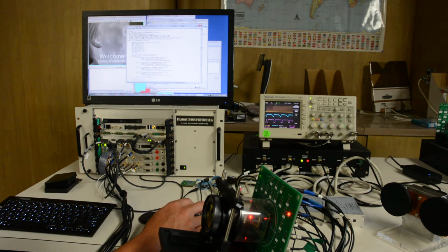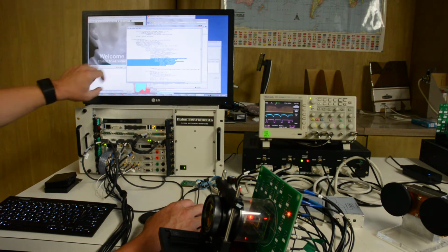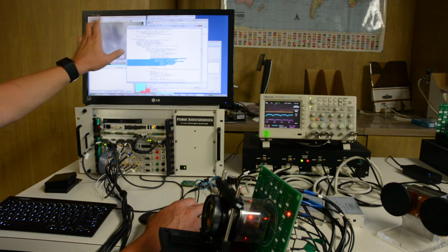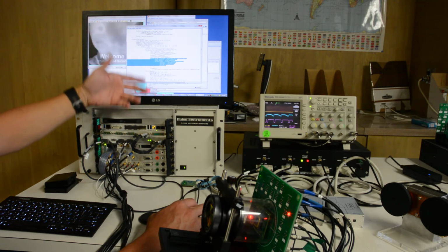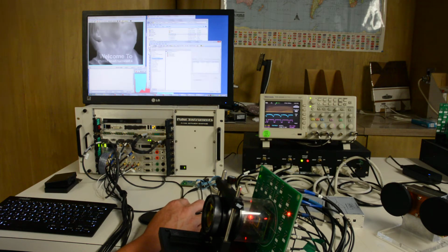where, for example, the 2-point non-uniformity correction, the guts of it really are here in about 8 lines of code. This is a very simple 2-point linear NUC. If you wanted to perform a 3- or 4-point piecewise linear NUC or a log linear NUC, you could do that here. You don't have to write an entire DLL. Just copy and paste this function, change the name, edit 8 lines of code, recompile, and then you can use that function to run your device while still retaining all the graphical, programming, and automation features of PyDATs.